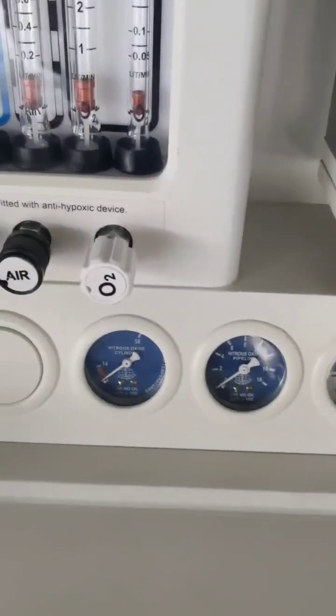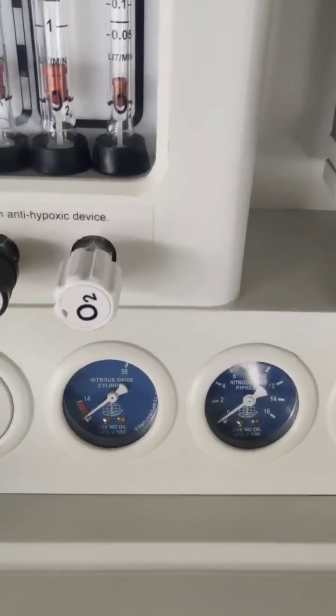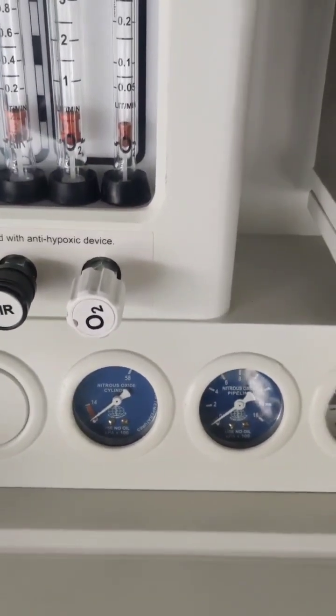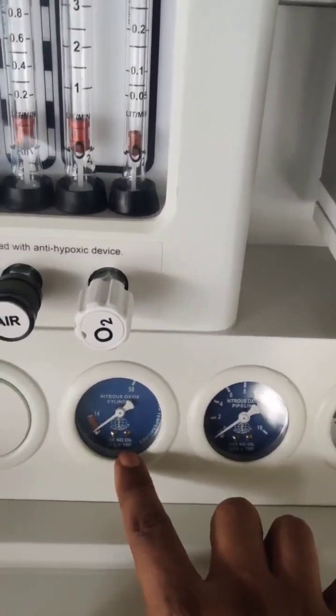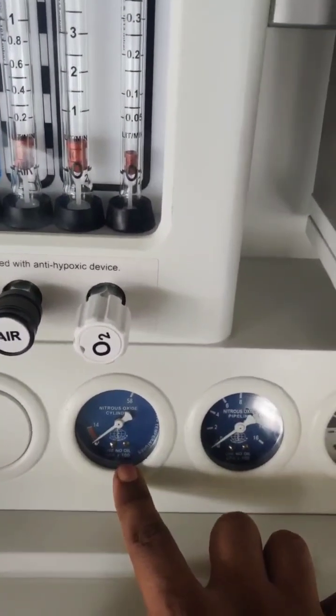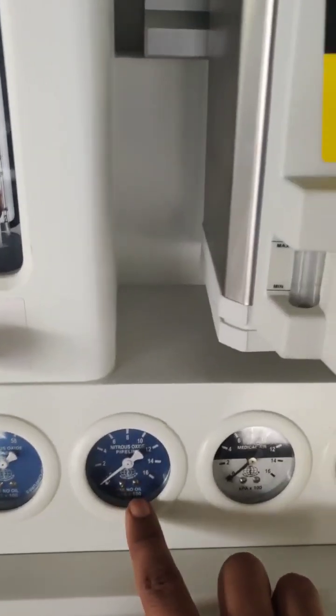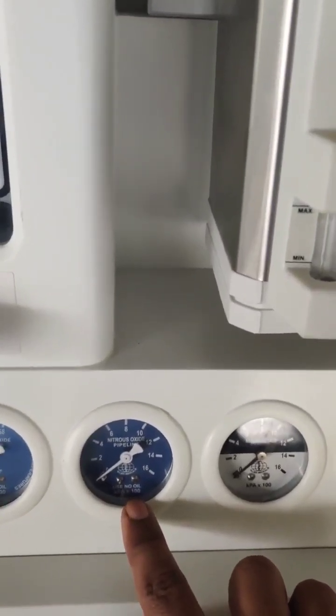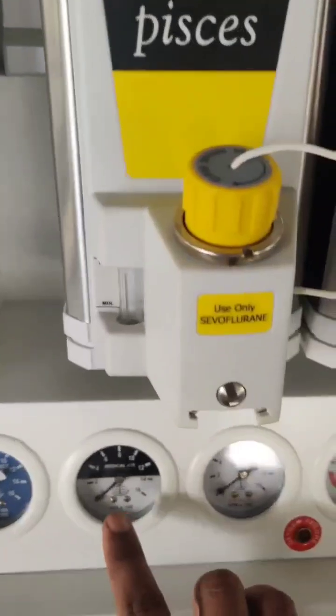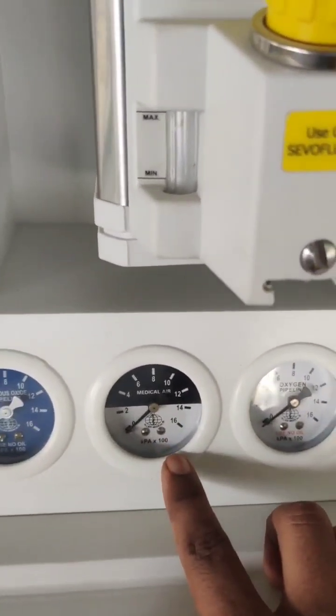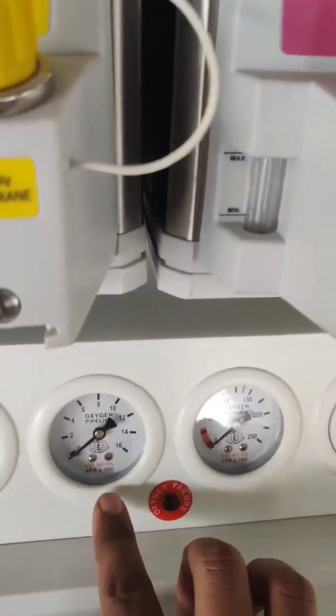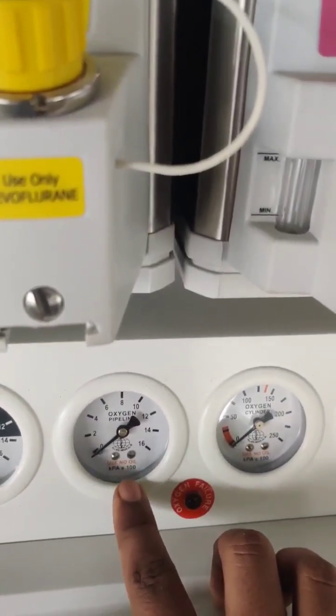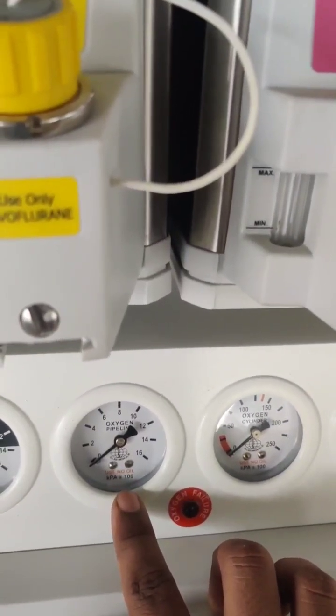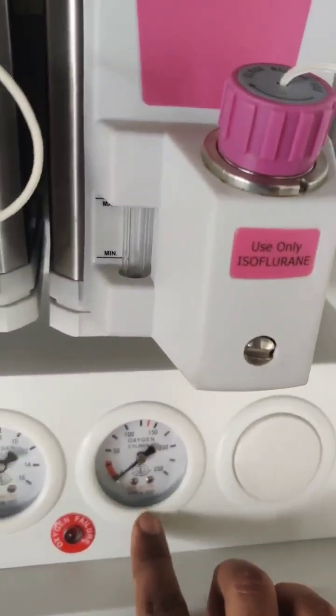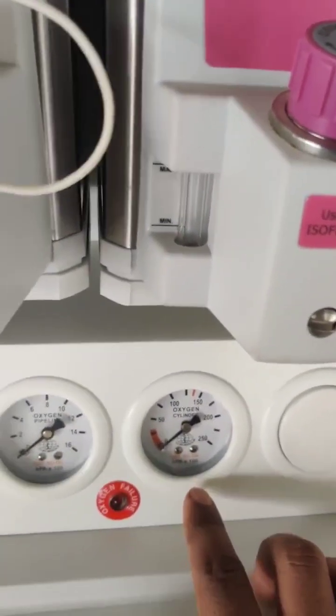Now we have the gauges. These are color coded, and each gauge indicates the pressure of the input gases. This gauge is blue in color, which means it is showing the pressure of the cylinder connected at the cylinder yoke. This is a color coded gauge for the pipeline system, this is for the pipeline system of the air, this shows the pressure of the oxygen pipeline system, and this is for the oxygen cylinder which is connected at the yoke at the back side.